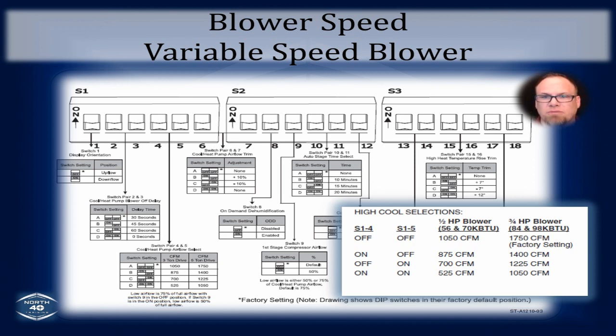Now, think about it. You've got a motor with a computer module at the end of it, and that motor with a computer module at the end of it is consistently trying to fight the resistance in that ductwork. The way that it does that is it's changing its configurations internally to increase the amount of torque that it can exert against that resistance. In doing so, the amp draw goes through the roof. So you've got a motor that's extremely efficient as long as it's in the application that it was designed for, which is 1 inch of static or less, and according to manufacturer specs, 0.5 inches of static or less. If you put it in that application, it will run much more efficiently than its counterpart in multi-speed blowers.